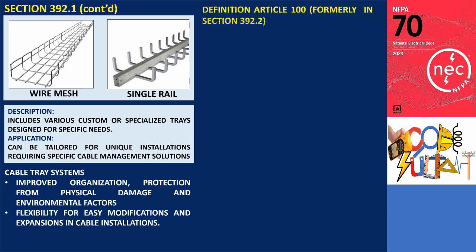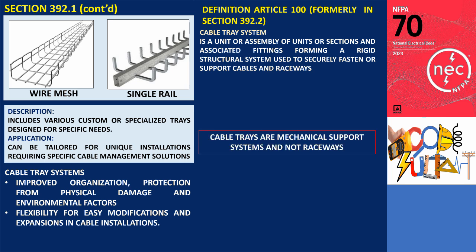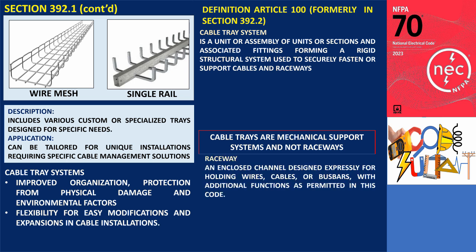The code defines a cable tray system as a unit or assembly of units or sections and associated fittings forming a rigid structural system used to securely fasten or support cables and raceways. This definition underscores the primary function of cable trays as mechanical support systems and not raceways. To further clarify this distinction, it's important to examine the definition of a raceway found in Article 100. A raceway is defined as an enclosed channel designed expressly for holding wires, cables, or busbars, with additional functions as permitted in this code.